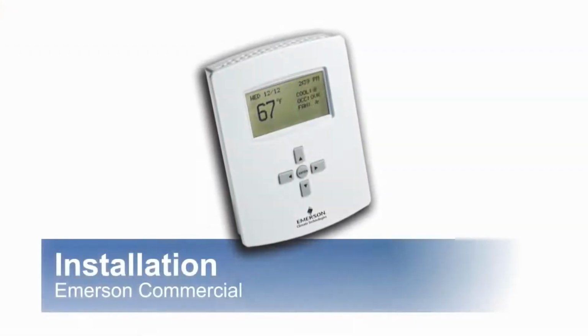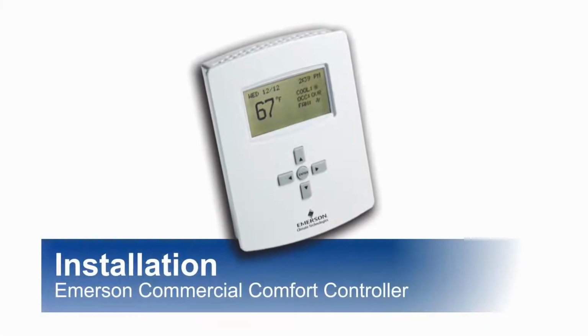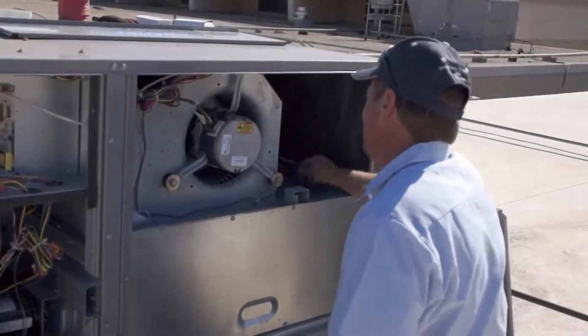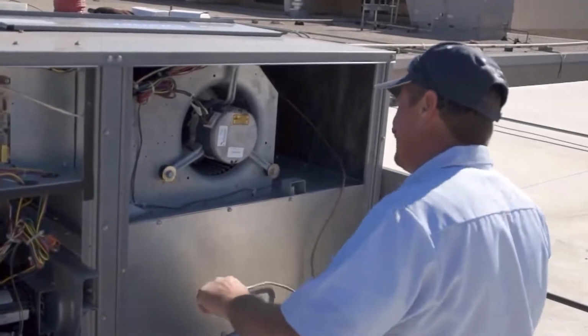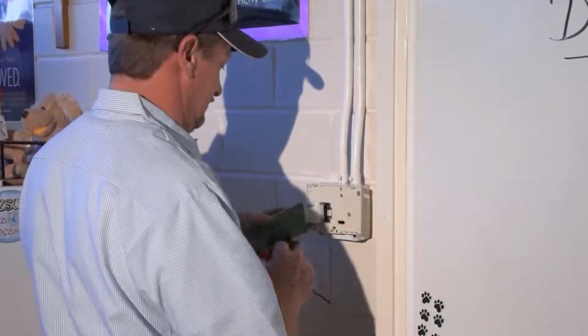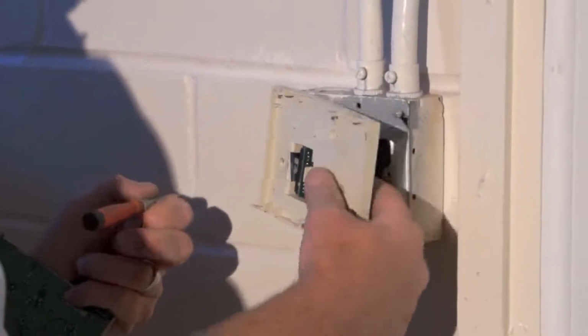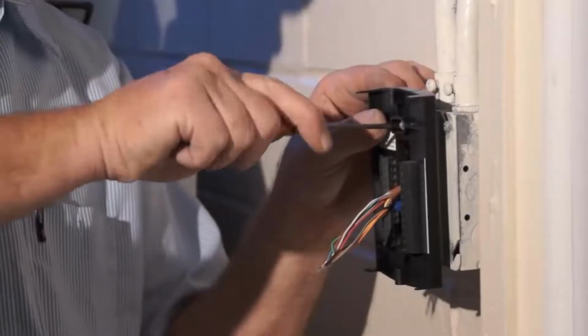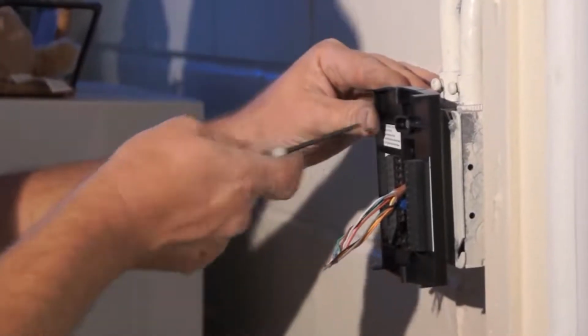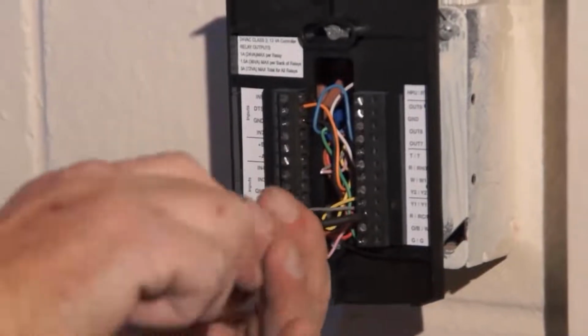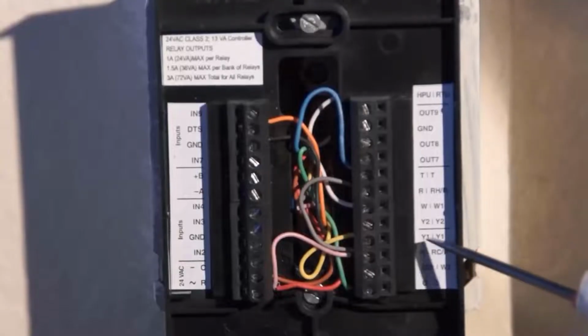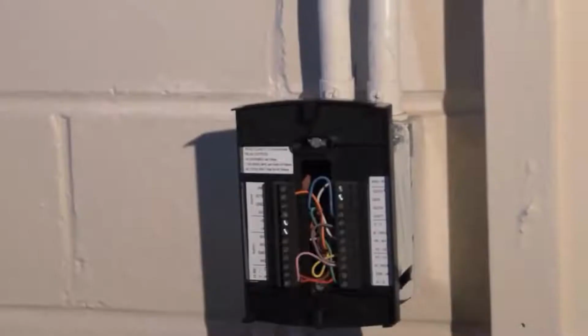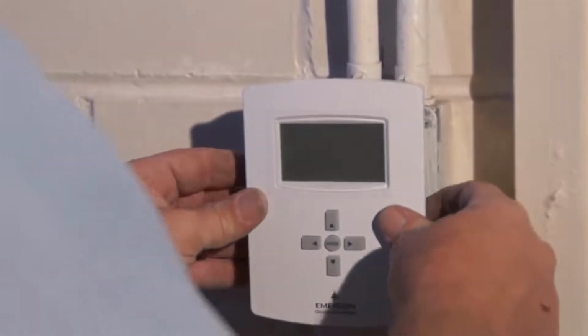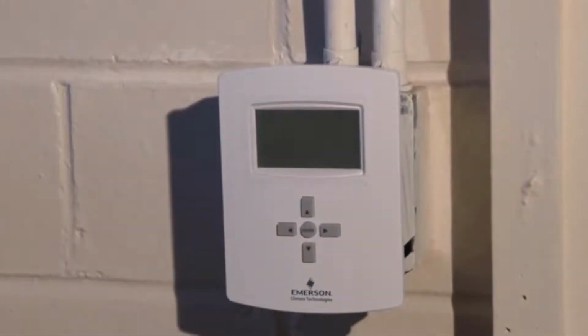You can now begin the installation of the Emerson Commercial Comfort Controller. The first step is to pull the appropriate wire from the rooftop unit back to the thermostat in the conditioned space. Once the wire is in place, mount the back plate. While wiring the comfort controller, be sure to record the chosen wire connections and colors. After snapping on the controller cover, it is time to head back up to the roof.